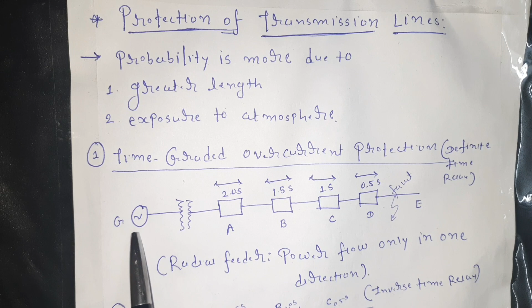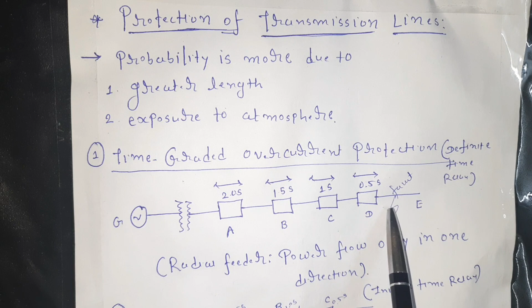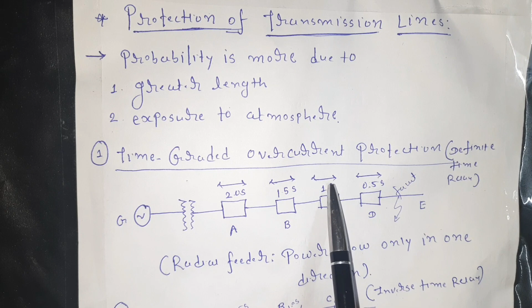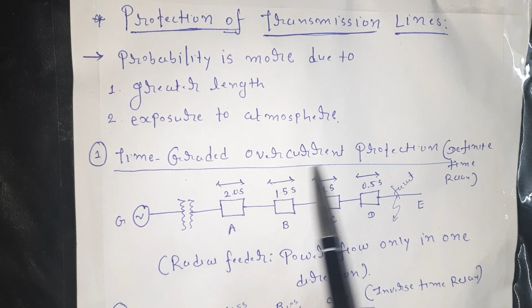But from the generating station, if the number of feeders in series are more, then what happens? As you have seen, if the fault is here, then this relay will operate at 0.5 seconds. Here it will operate at 1 second. So as we are moving further from the generating station, it will operate very quickly. But if the fault is nearer to the generating station, it will take more time. And as far as the stability of the system is concerned, the maximum time to clear the fault is 2 seconds.